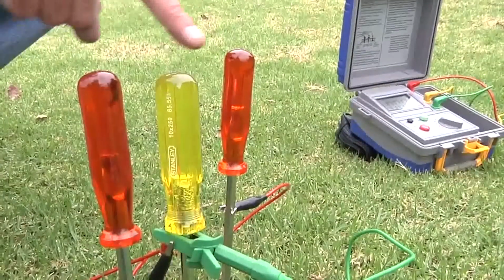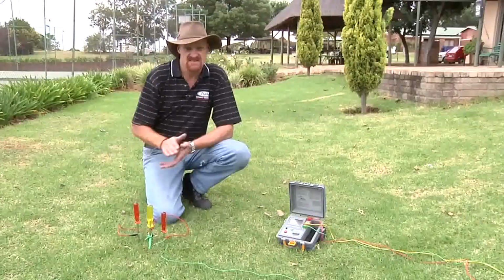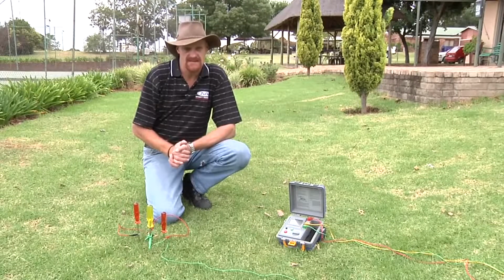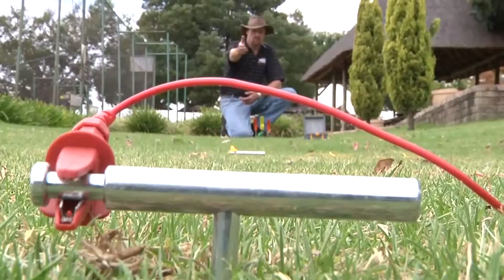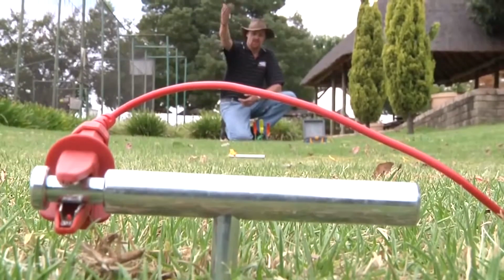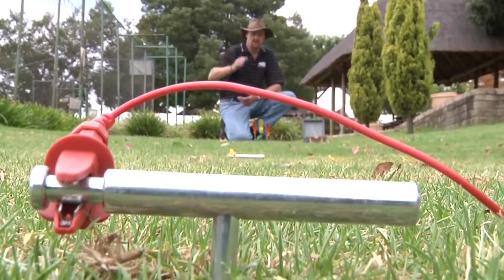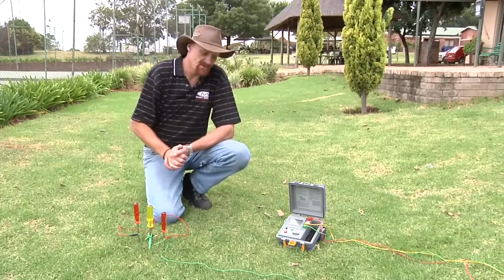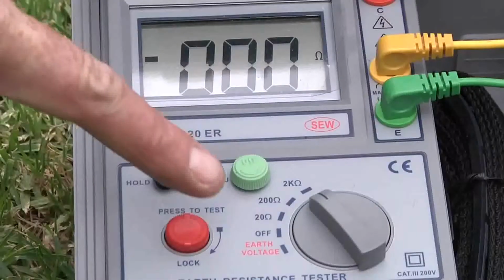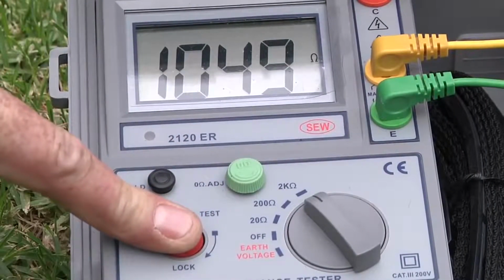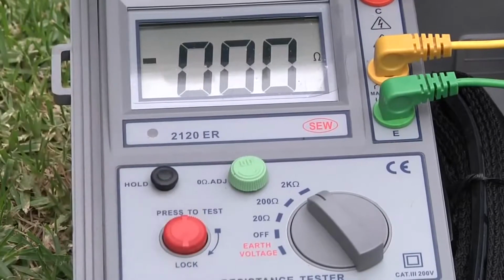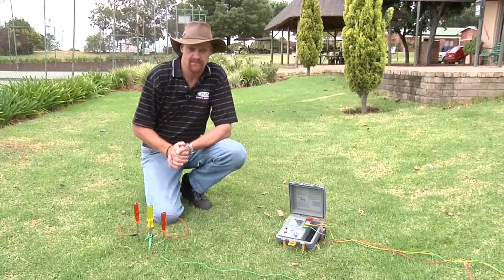What we have here are our 3 earth probes simulating our 3 earth spikes. We then have our potential probe, the yellow one, and the current probe, the red one, on our digital earth resistance meter. We have a current reading which simulates that our earthing is not that great.